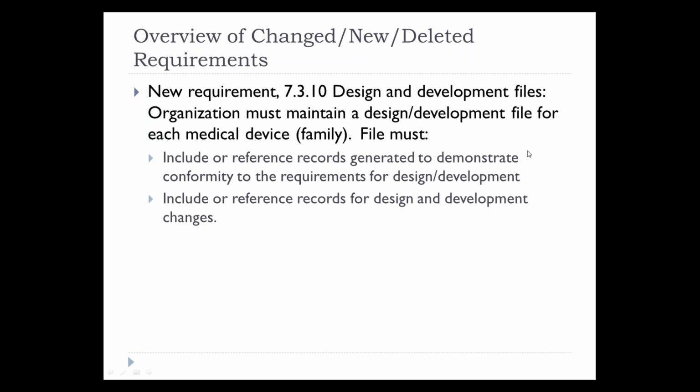New requirement 7.3.10, design and development files. The organization has to maintain a design and development file for each medical device or medical device family. The file must include or reference records generated to demonstrate conformity to the requirements for design and development, and include or reference records for design and development changes.